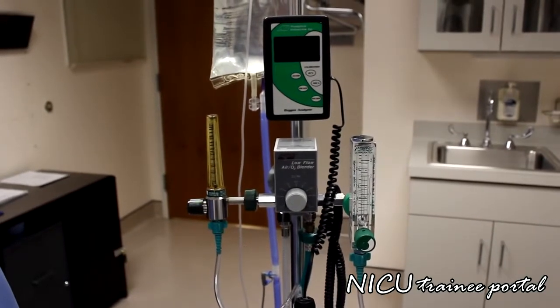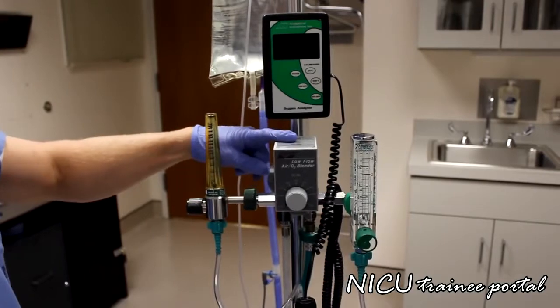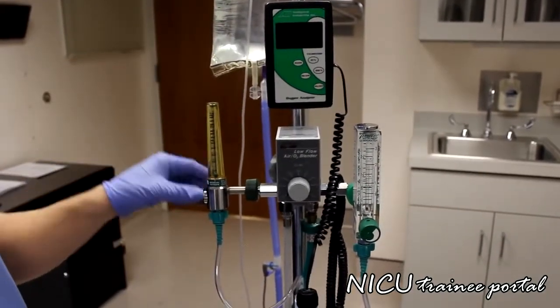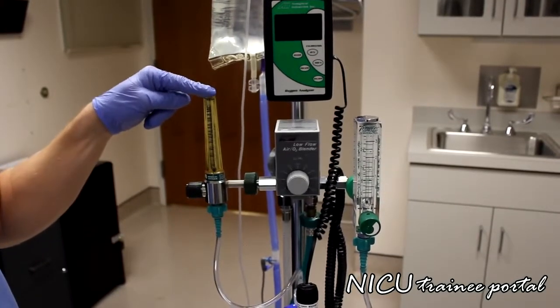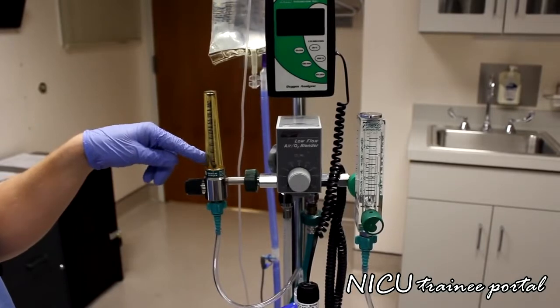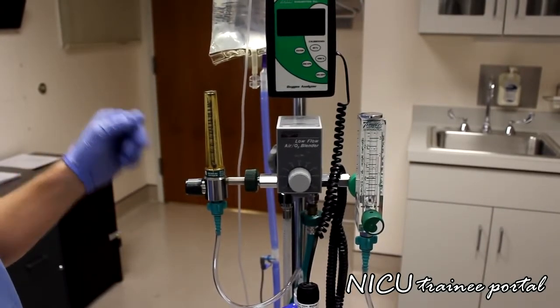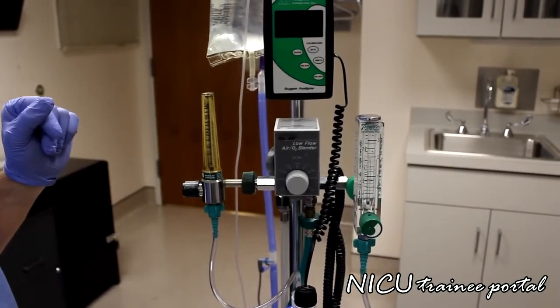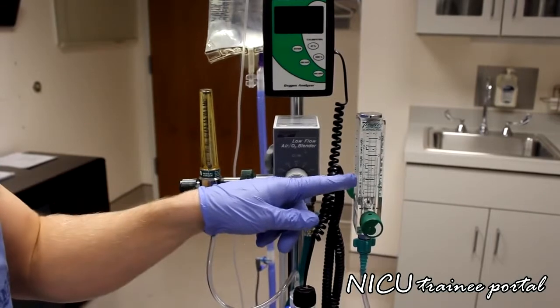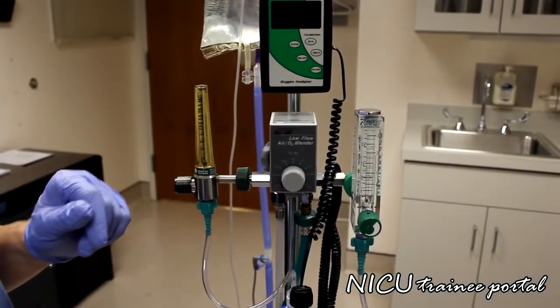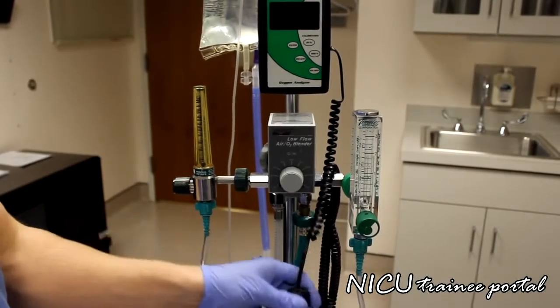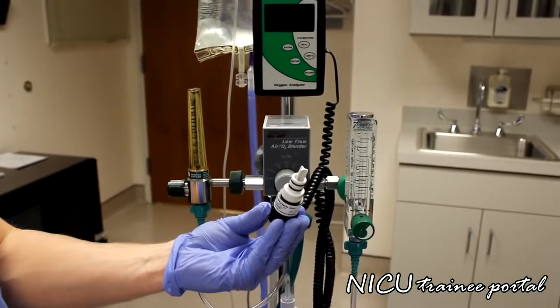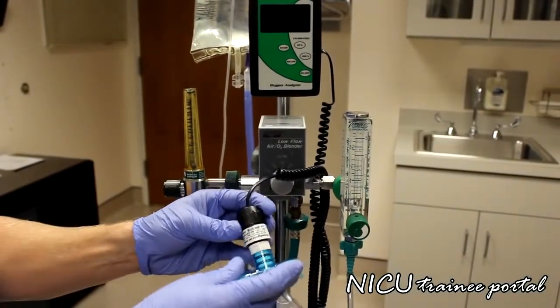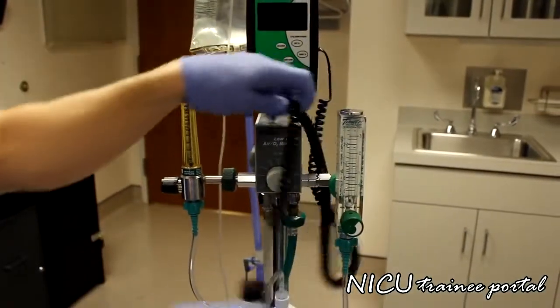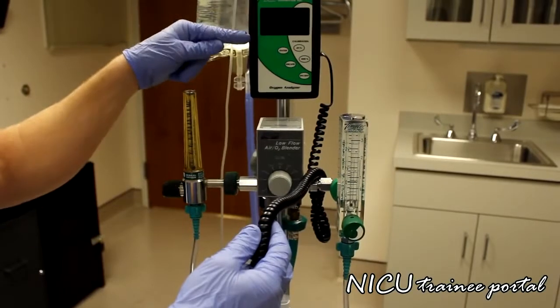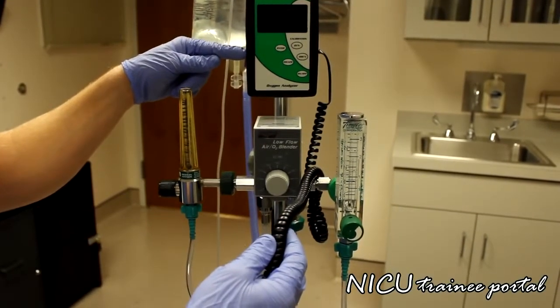Okay, so on this particular high flow setup, we have our oxygen blender connected to 2 different flow meters. The first flow meter is what we will be driving or powering our high flow circuit with, typically between 1 and about 8 liters of flow. And this is the one that's connected directly to the water chamber. The next flow meter that we have here is strictly for analyzing our oxygen content. This one is connected to our oxygen analyzer. So this goes into this piece, and then our oxygen analyzer is connected up here, and this is what is going to be reading our FiO2.